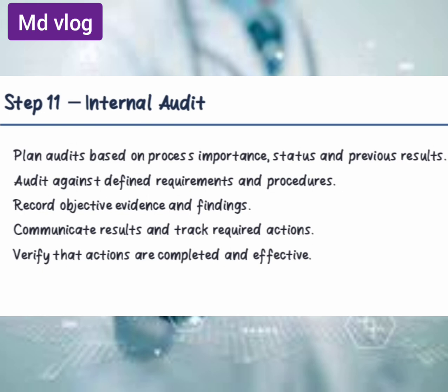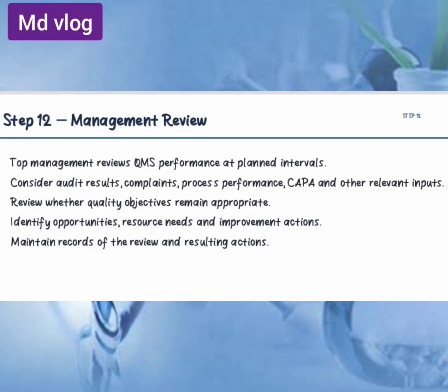Internal audit is a health check of the QMS. Auditors should look for objective evidence rather than relying only on verbal confirmation. Twelfth is management review. The management review connects operational data to management decisions. It is where leadership evaluates whether the QMS remains suitable, adequate, and effective.